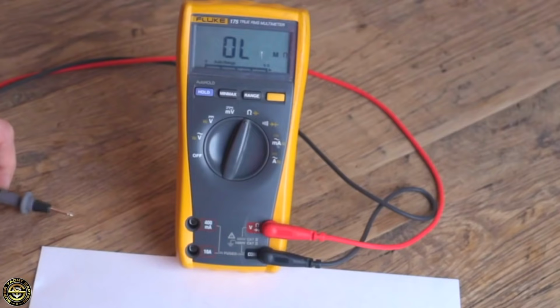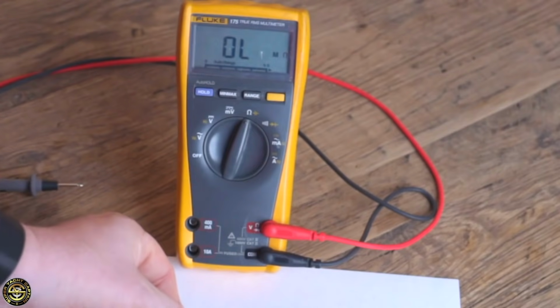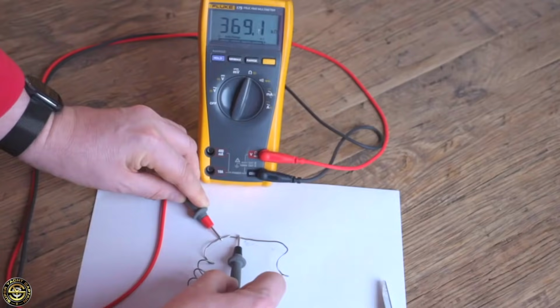If the earthing cable was completely broken, you would just get an incomplete circuit, because there's no way to get from point A to point B. Very high resistance means there's something there, but it's very poor. It also says that when they energized one of the load bank elements, there are 3 elements in this unit, so you can turn them on independently, one at a time, an electrical arc was observed between the load bank earth connection termination and the casing of the load bank.